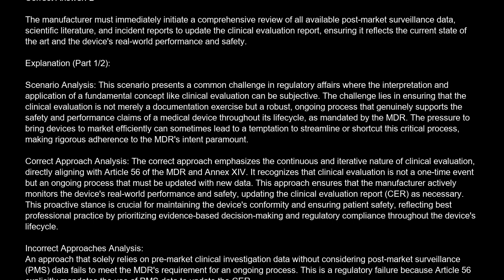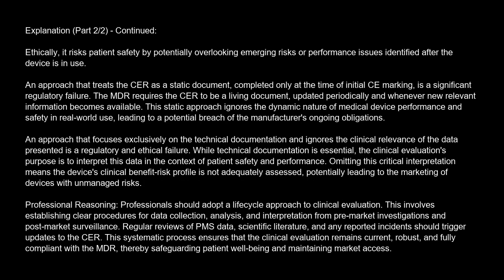Incorrect approaches analysis. An approach that solely relies on pre-market clinical investigation data without considering post-market surveillance, PMS, data fails to meet the MDR's requirement for an ongoing process. This is a regulatory failure because Article 56 explicitly mandates the use of PMS data to update the CER. Ethically, it risks patient safety by potentially overlooking emerging risks or performance issues identified after the device is in use.